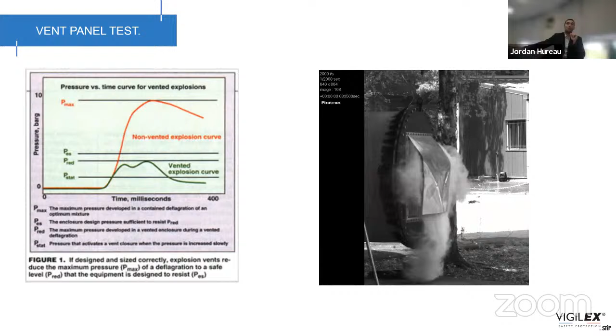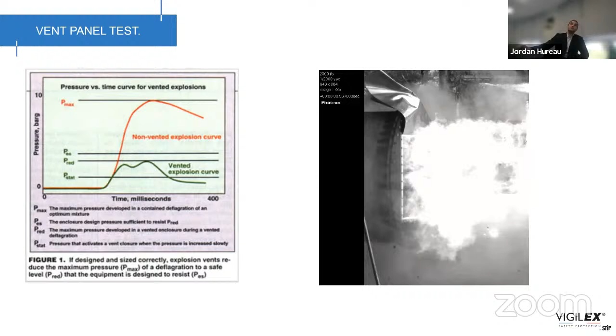And you see on the vent panel that it opens on three sides. Only one side is always standing on the vessel that you want to protect, because if it were not standing on the vessel, it would be thrown away. It can hurt somebody, of course. So you see the idea is to release the explosion pressure outside.